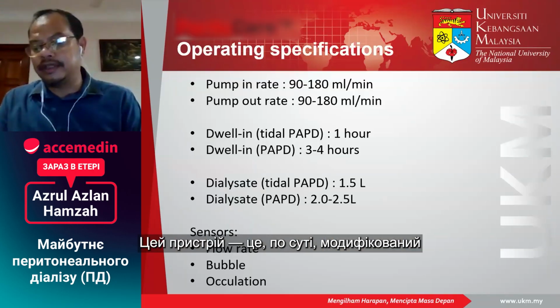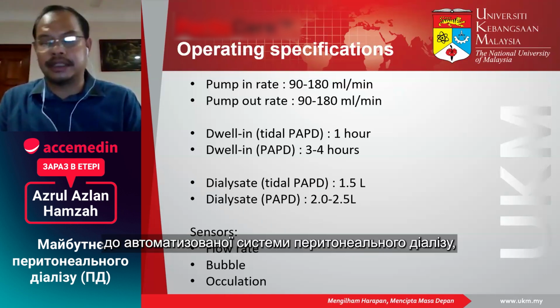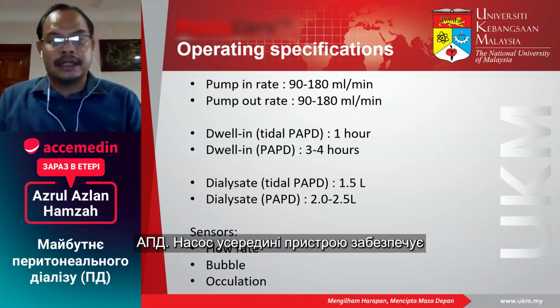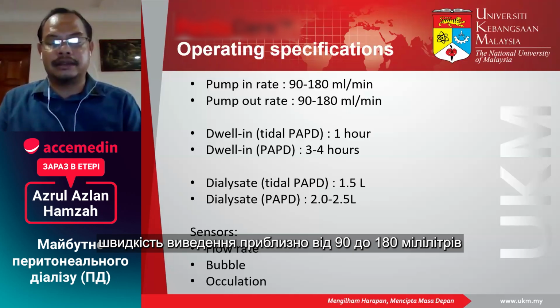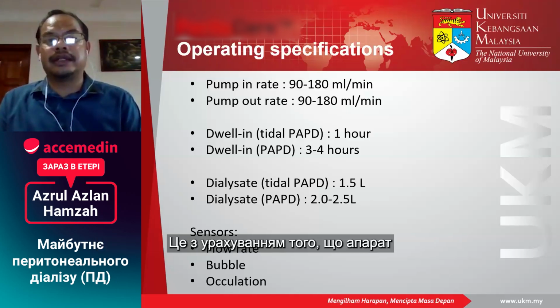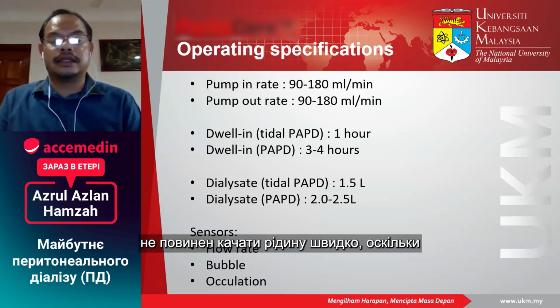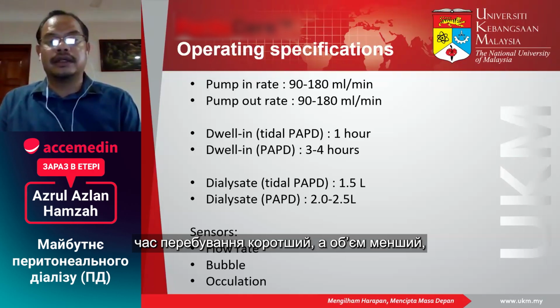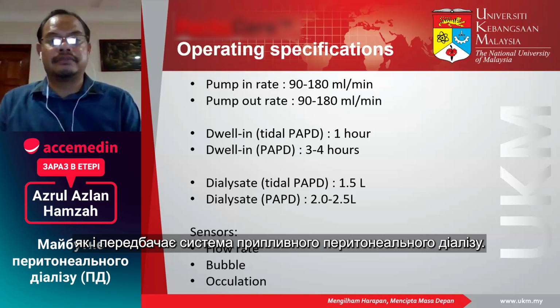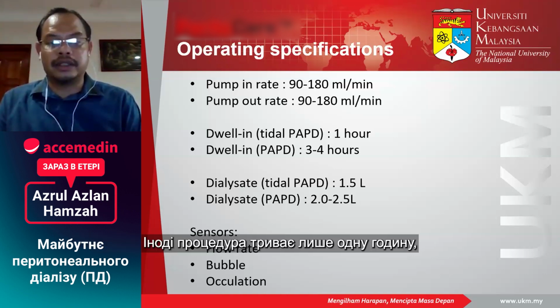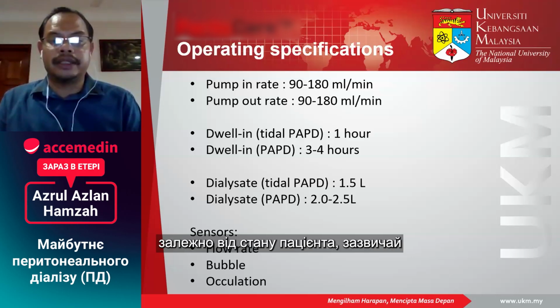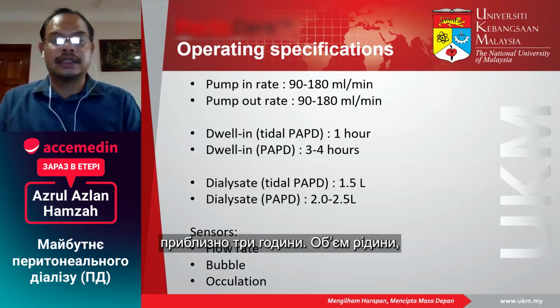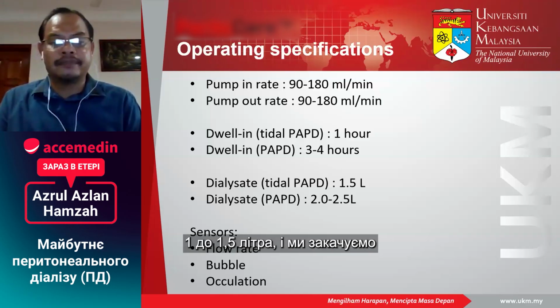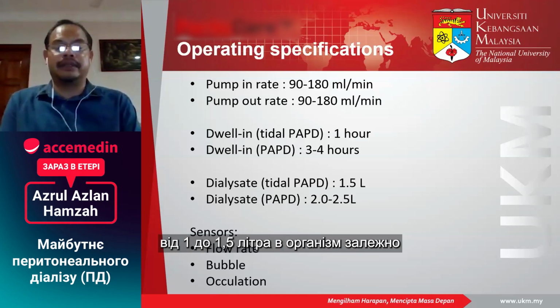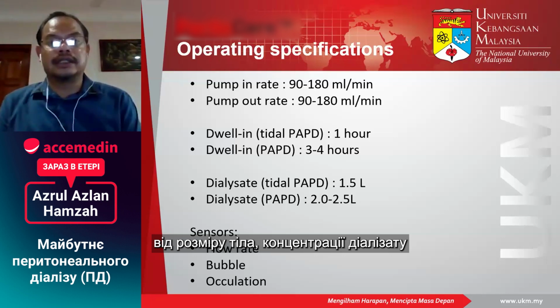This device is a cycler, and we have improved the cycler to become an automatic peritoneal dialysis system (APD), and basically the pump in and pump out rate is about 90 to 180 milliliters per minute. This takes into account that the machine does not have to pump fast, because the dwell time is less, and the dwell amount is also less in a tidal peritoneal dialysis system. So sometimes we dwell for only 1 hour, depending on the condition of the patient, usually around 3 hours. The tidal amount in the body is around 1 to 1.5, and we pump 1 liter to 1.5 into the body, depending on body weight, size, physical condition, concentration of the dialysate, and so on.